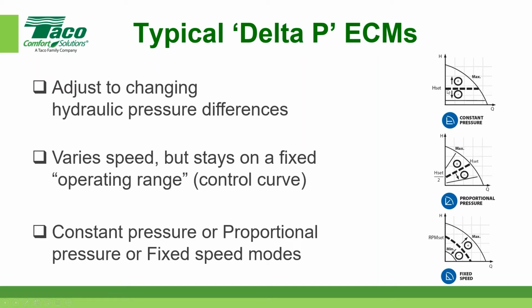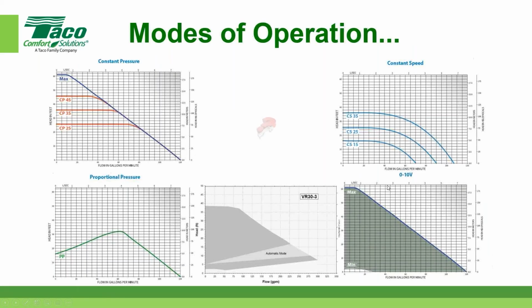This would be constant pressure because you get a constant operating range that's straight across at a particular fixed amount of resistance. You see proportional because it's kind of pitched down here. That would be the proportional pressure operating range. Then under fixed speed, you're actually going to see a curve, and now all you're doing is turning the RPM up or down within that particular mode. Again, constant pressure, proportional pressure, or fixed speed.